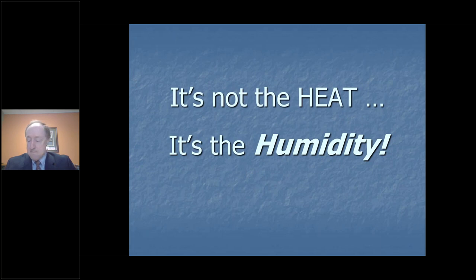Okay, next question is: with a pre-cooling sensible cooling system, air can reach up to 100% relative humidity. Desiccant moisture absorption, on which basis will it be efficient: dew point, RH or absolute humidity?